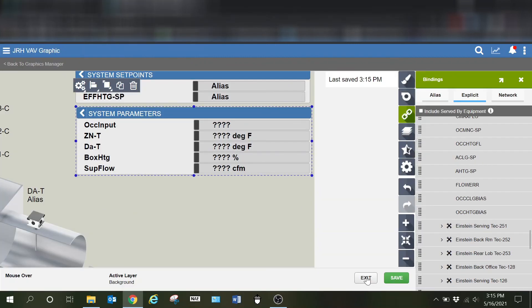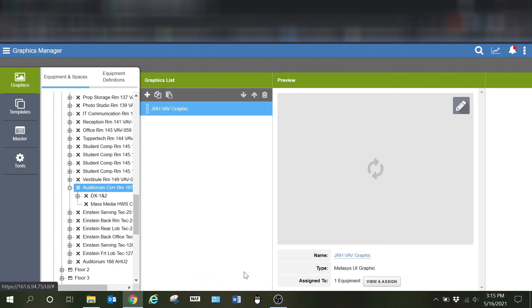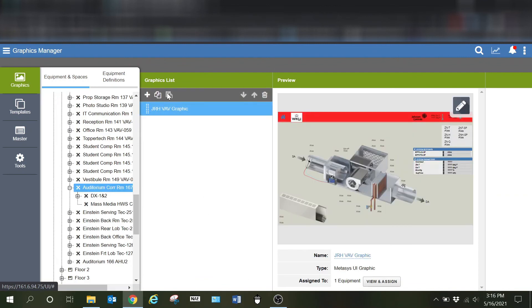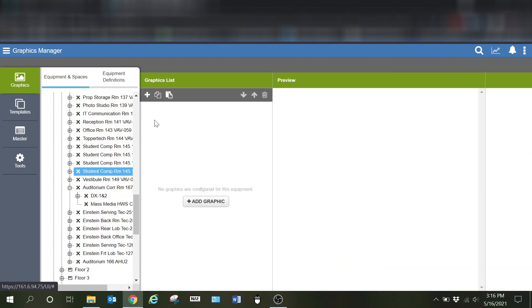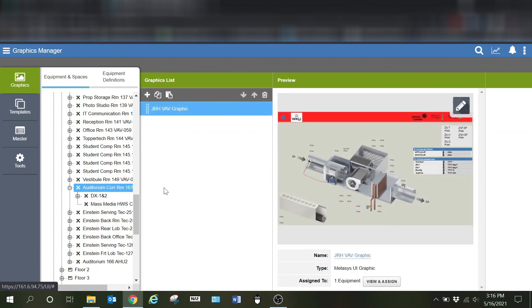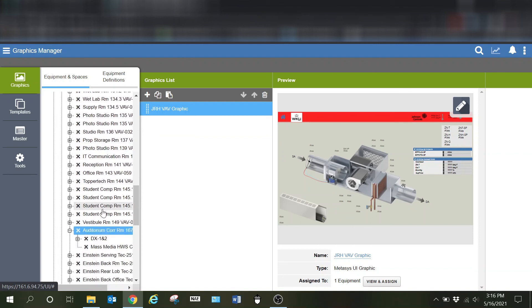I can go back in and delete it out for this particular box or whatever. Now that we have that set up, one thing that is a little bit of a time saver on that is I have the option here of copying. I can actually go in and copy this particular graphic. Once I get it all set up and customized the way that I want it, I simply hit copy and then I can go down to any of the other boxes and simply hit the paste button and it will paste everything that I did in that first graphic onto that other one. And that's how you can go in. If you have a lot of boxes that are identical, once you get one graphic set up to work for that box, you can simply paste it into any of the other VAVs or any of the other pieces of equipment that are identical to it. If there are a few small differences, you may have to go back in to tweak those individually. However, that is a big time saver of being able to do that.